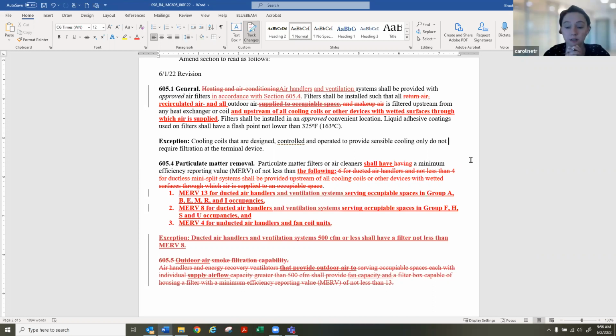I'm sorry, Eric, you're just talking about not having to filter the exhaust airstream that is leaving? Yeah. If it's exhausting and leaving and not being reintroduced, it doesn't seem like that needs to be filtered at all. It's not the intent. Well, by code it does, because it's upstream of a heat exchanger. And Eric, is that a byproduct of the deletion of "supplied to occupiable space"?